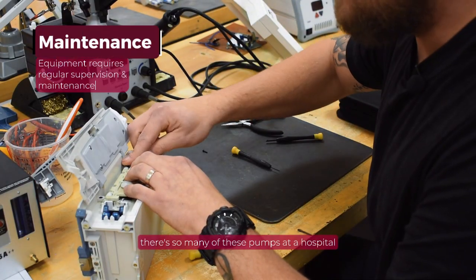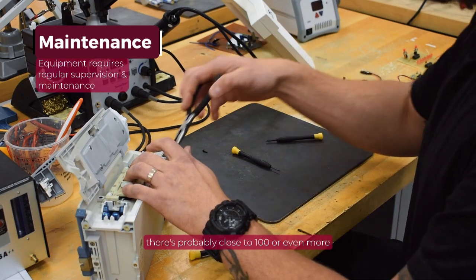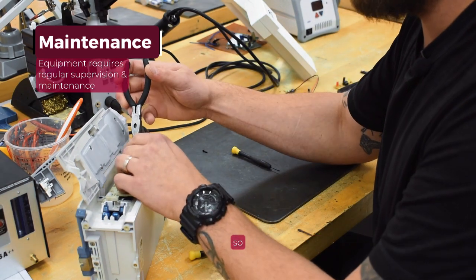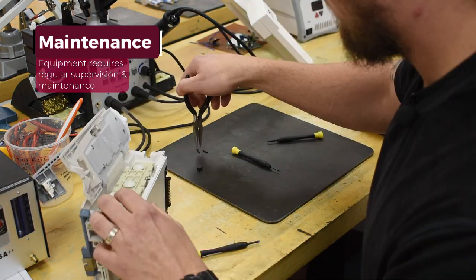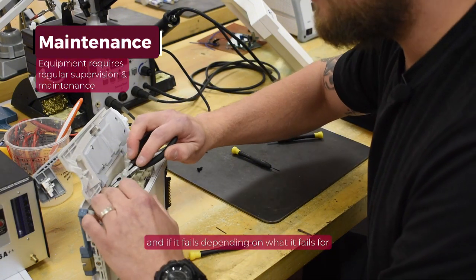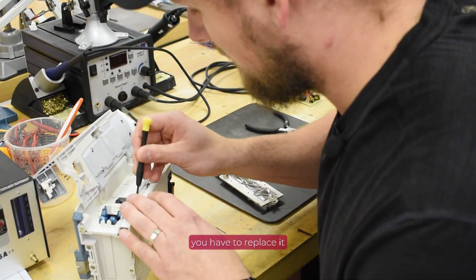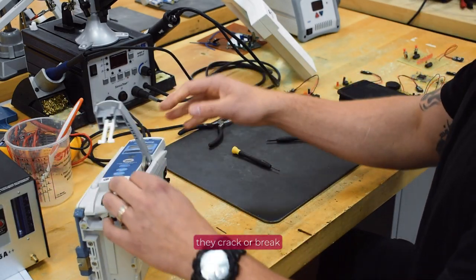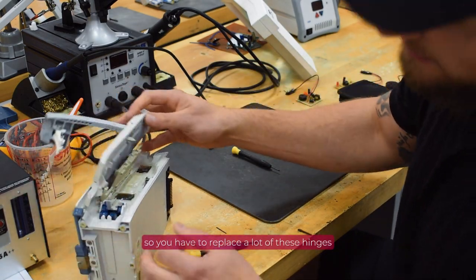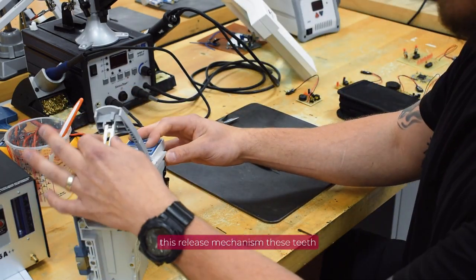There's so many of these pumps at a hospital, there's probably close to 100 or even more. So they're kind of a frequent inspection you have to do. And if it fails, depending on what it fails for, you have to replace it. If a part cracks or breaks, you have to replace a lot of these hinges, this release mechanism, these teeth.